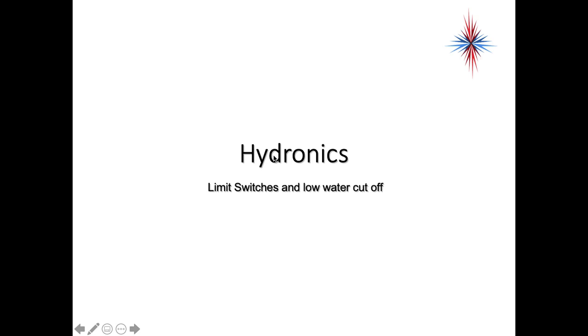In this video we're going to talk a little bit more about limit switches and low water cutoffs. These are two extremely important safety devices in a hydronic heating system, and for low water cutoffs, sometimes you find them in cooling systems as well. Limit switches can either be a safety device, which is their primary purpose, but they can also be operating devices, so keep that in mind about where we use them.